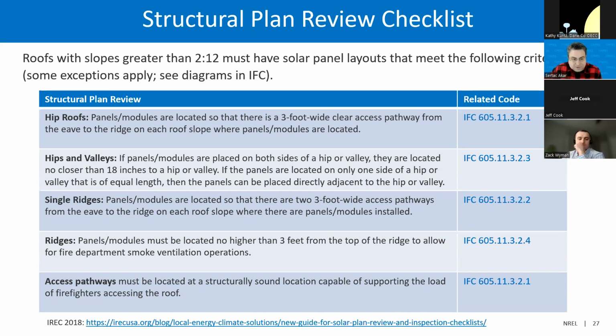For single ridges, panels or modules are located so that there's a 3-foot wide access pathway from the eave to the ridge on each roof side where the panels and modules are installed. And for access at the ridges, the panels or modules must be located no higher than 3 feet from the top of the ridge, in order to allow fire department smoke ventilation operations. The access pathways must be located at a structurally sound location capable of supporting the load of firefighters accessing the roof. These are actually in line with fire and safety requirements, but it's also part of a structural plan review.